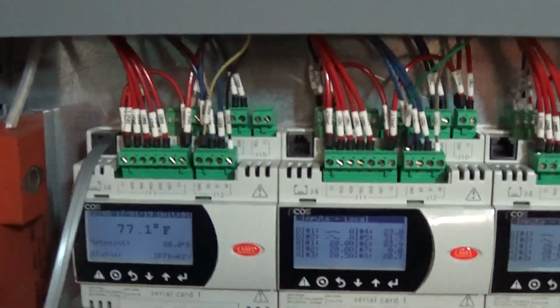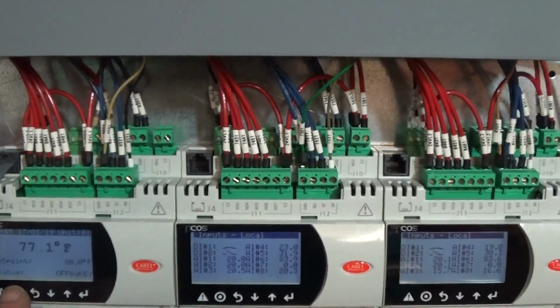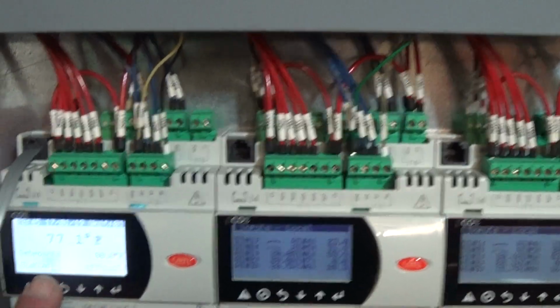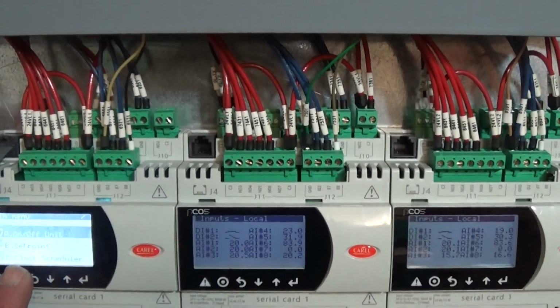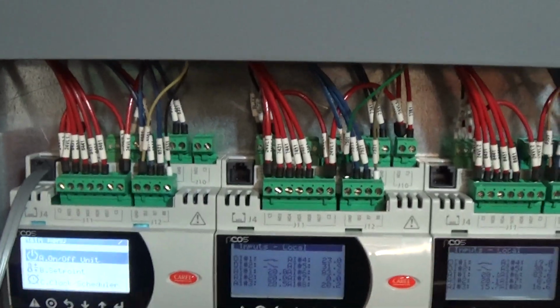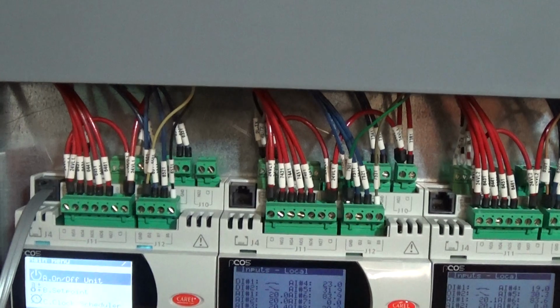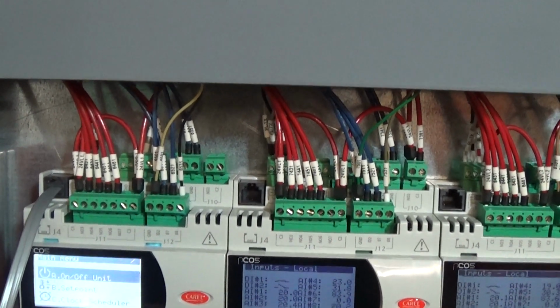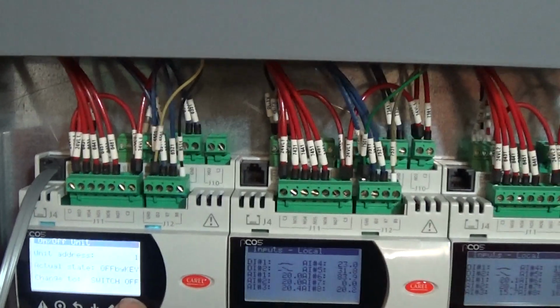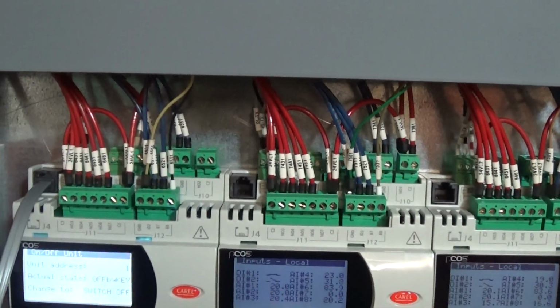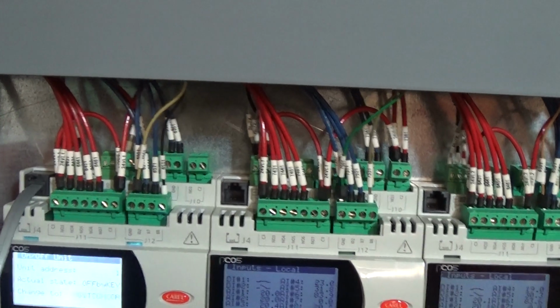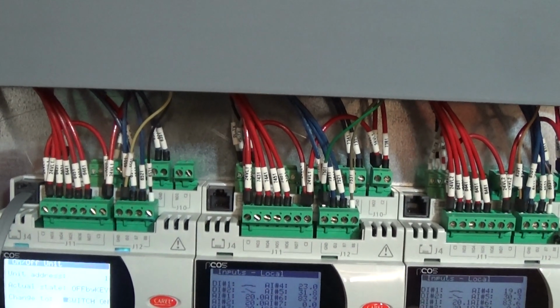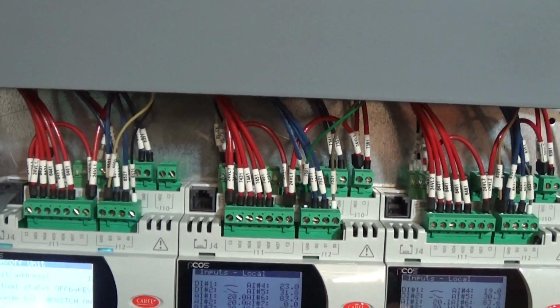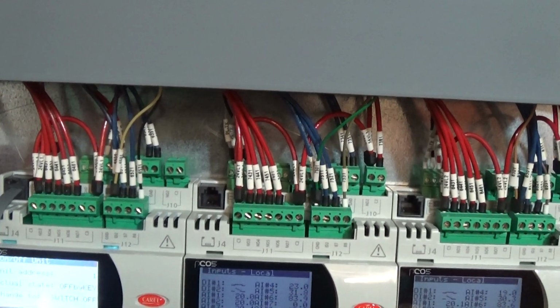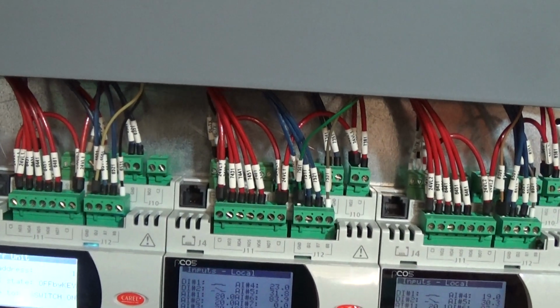Now, this unit is in the off position. We're going to turn it on by the front panel, and that's the first listing on the menu, the unit on/off, and it's highlighted. So what we'll do is hit the enter key, and then hit enter again, and then we're going to scroll down or up, either way, so that it reads switch on. I'll show you that you can go up too, and then enter again. That will activate the pumps.